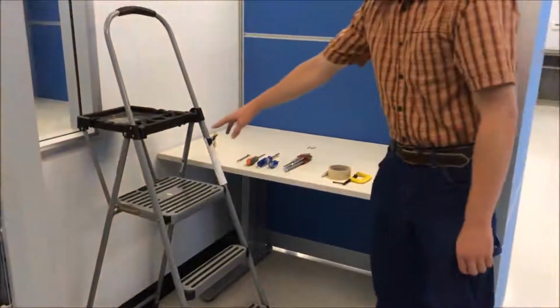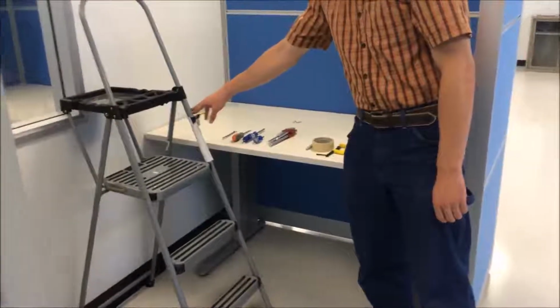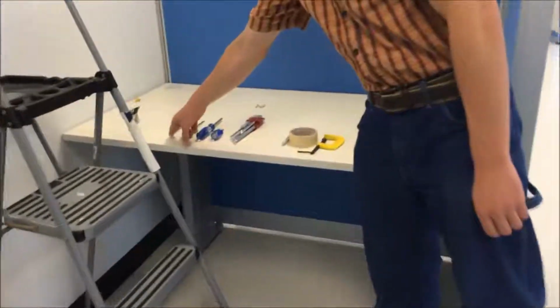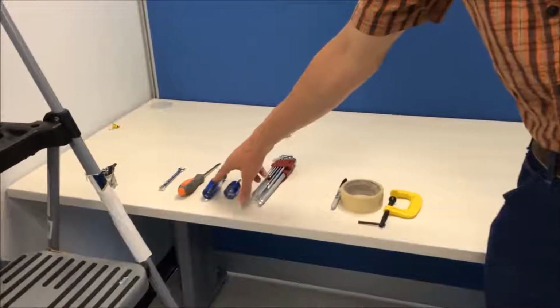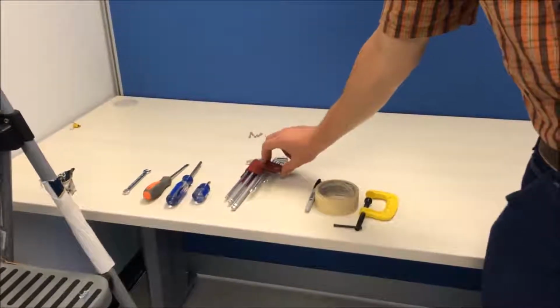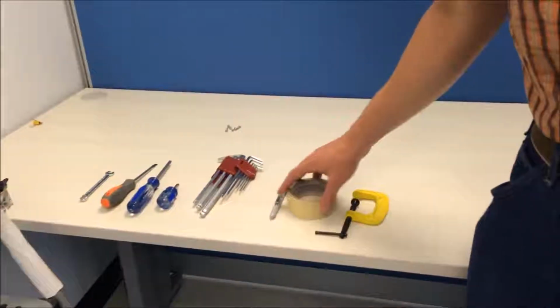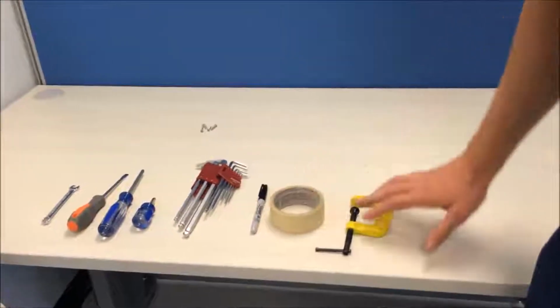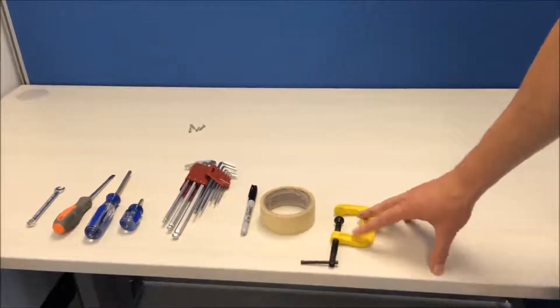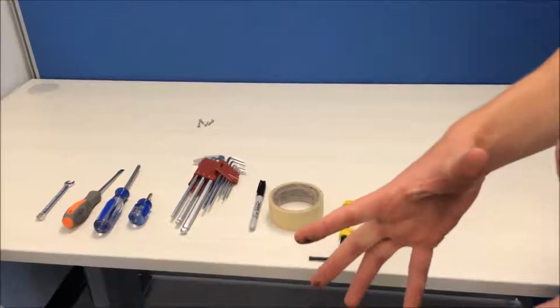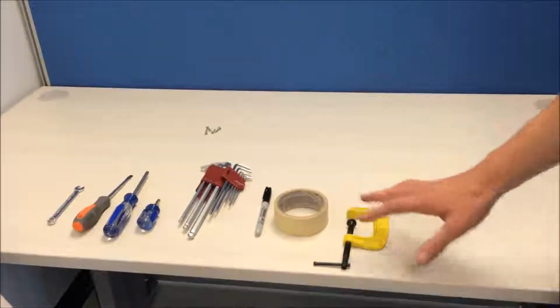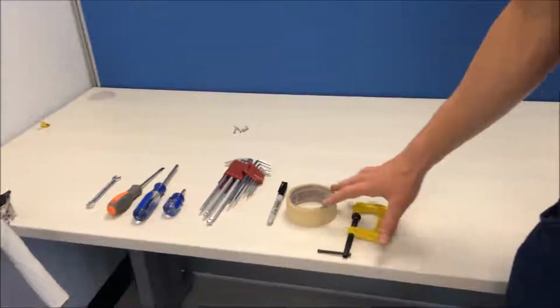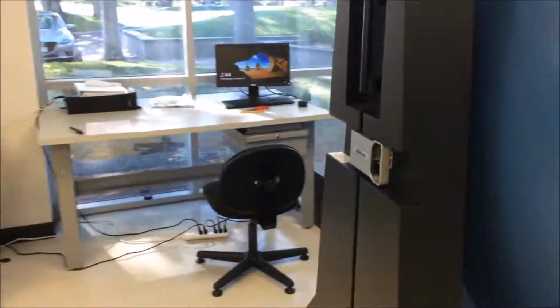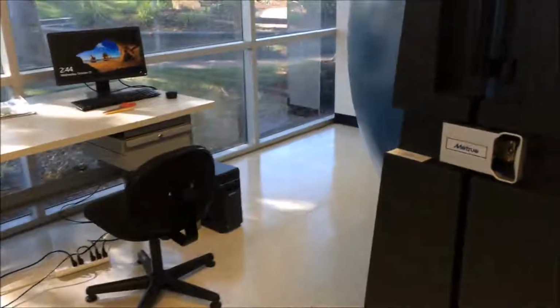And then over here I have a few tools that I will need to put the sphere together. So I have a step-up ladder, which will be useful for the electrical cable. I have a 3/16 wrench, flathead screwdriver, Phillips screwdriver, a standard Allen head set, Sharpie and tape if you want to label your wiring inside, and then I use a clamp sometimes to help with attaching the integration sphere hinges, to hold it together while I put the hinge in place. And then finally you'll need a computer. I have one over there. That's all that you will need to put the sphere system together.